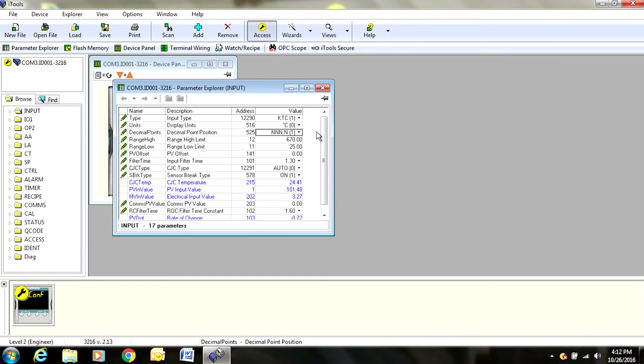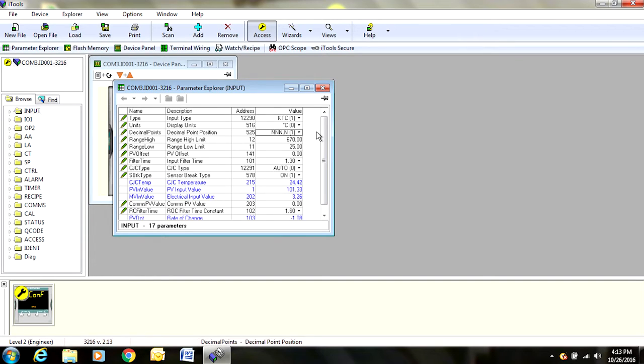You don't want to set it at 401 because if it is at 401 and the calibrator happens to overshoot the 400, that may happen. It will actually shut off. So if you give yourself a little bit of leeway, set it at 450, you will be OK. If it reaches that point, it will actually turn off, so you want to make sure to give yourself some room. We set them from the lab at 670. That is to avoid melting the block inside of the calibrator.